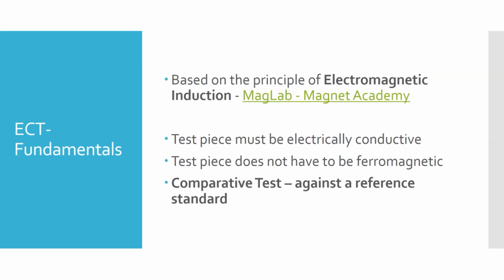So eddy current testing, at its fundamental level, relies on electromagnetic induction. I'm going to pull this video up here in just a second. But what that means, because it is dealing with electromagnetic induction, is that the piece has to be electrically conductive. In order to build an electromagnetic field in it, current has to be able to flow through it. And so, again, that test piece doesn't have to be ferromagnetic, like aluminum or titanium, but it does have to be conductive. And then it's comparative. We have to have that reference standard.